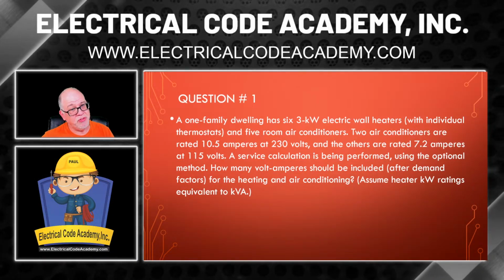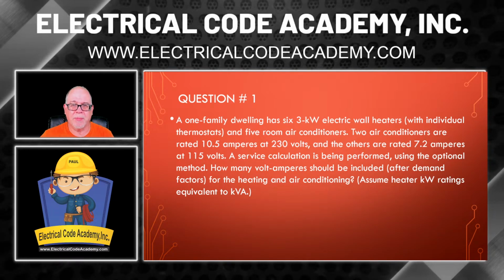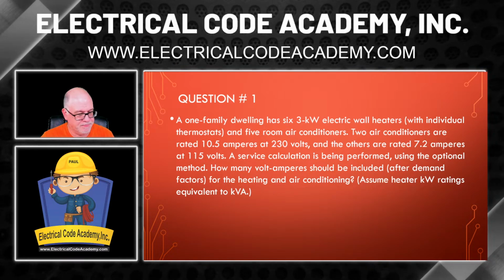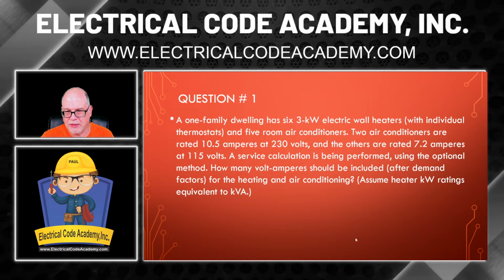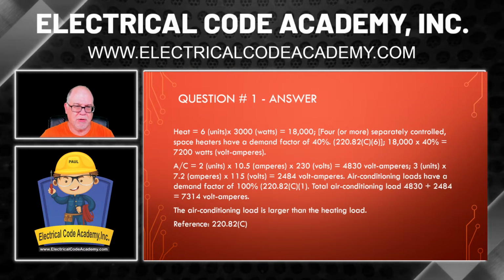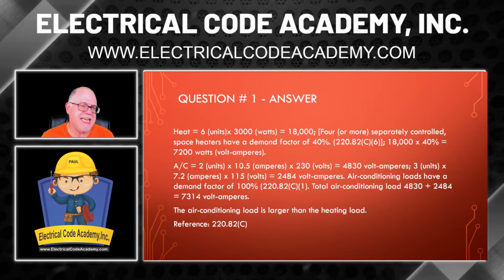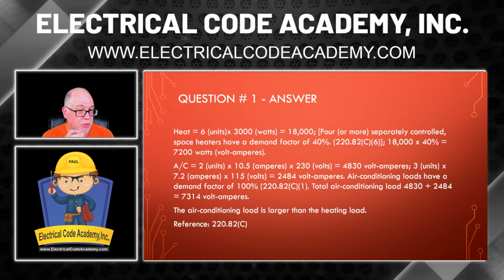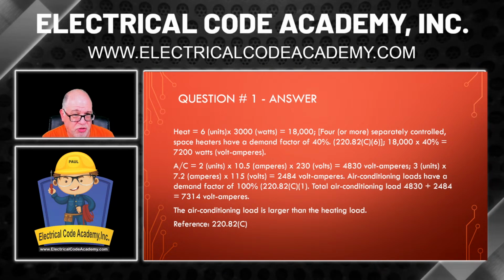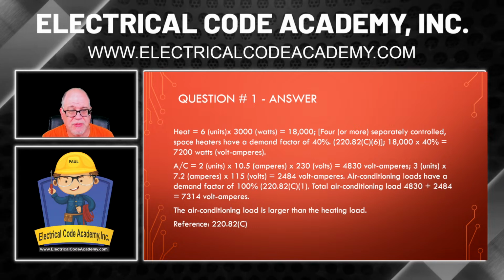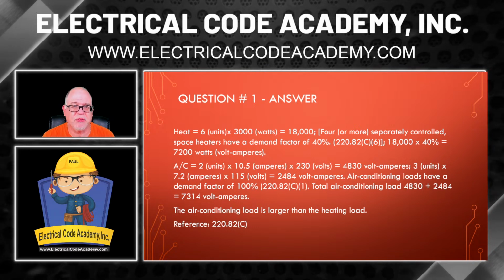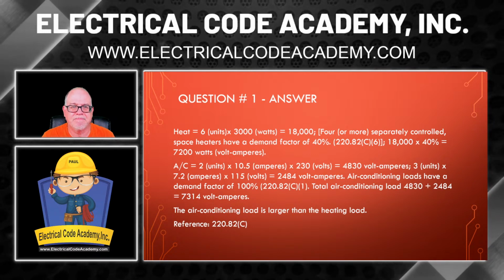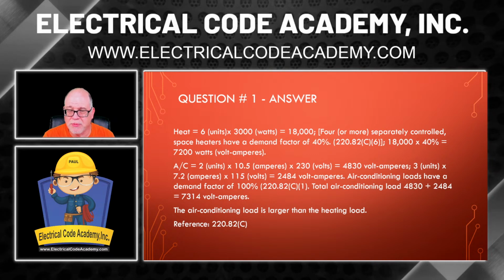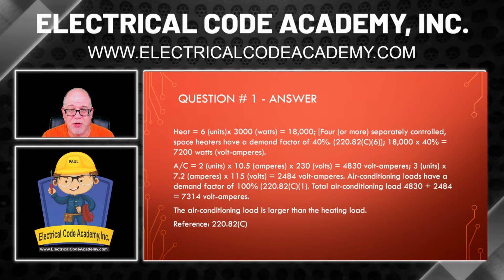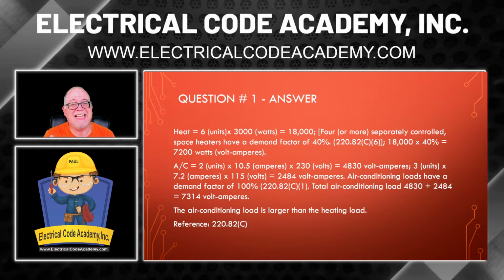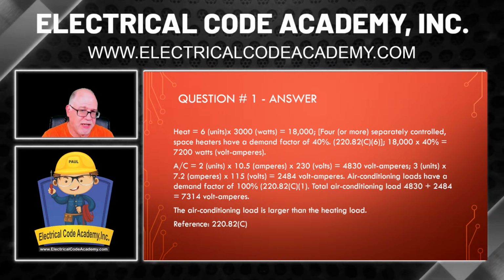So here was our question, and we got to do a couple things in order to get there. All right. So let's go on and start working the math. Okay, first thing, let's knock that heat out. There was 6 of them. There was 3,000 watts each, or 3 kW each. So we're going to work this out. So 6 times 3,000 or 6 times 3 kW, that would equal 18 kW. But in this case, it's 18,000, the way we're working it out here.